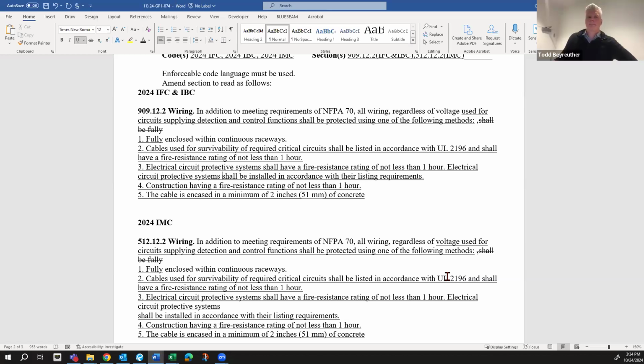Hi guys, sorry, I just got in from another meeting I had to jump over. So the background of this is, right now, 909.12.2 says all wiring regardless of voltage shall be run in a continuous raceway. When you have a fire alarm system that would be installed regardless of the pressurization system, in a full coverage jurisdiction like King County or Tukwila or Puyallup, where every single smoke detector in the fire alarm system isn't there for pressurization, it's there for fire alarm detection, that continuous raceway basically with the AHJs encompasses everything. They've pushed back and said, well, you have to deal with the electrical inspectors on it. Electrical inspectors aren't looking at IBC or IMC or IFC 909.12.2 for it.